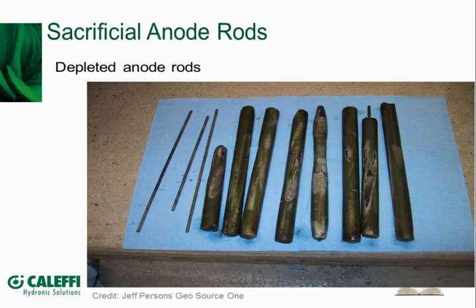The solution for this problem was to install a polysulfone, high-temperature plastic container in the recirculating line for their hot water system and put some magnesium rod sacrificial anodes into it. And so here you see a couple of depleted sacrificial anode rods with their center cores on the left side, and some other rods in the process of being depleted that were taken out of that canister. Once those sacrificial anodes were installed in the system, the green stains in the sink stopped, and we've not been back to replace any pumps, and thank goodness there haven't been any perforations in the copper lines in that pump.